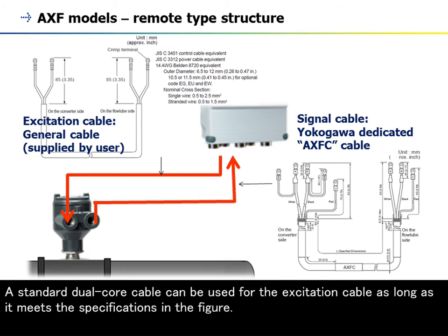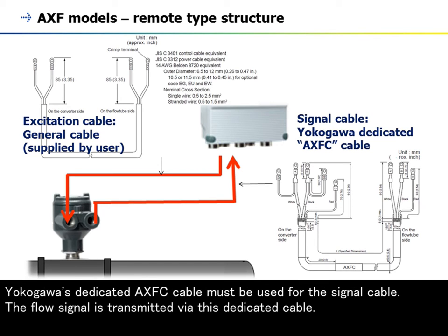A standard dual-core cable can be used for the excitation cable as long as it meets the specifications in the figure. Yokogawa's dedicated AXFC cable must be used for the signal cable. The flow signal is transmitted via this dedicated cable.